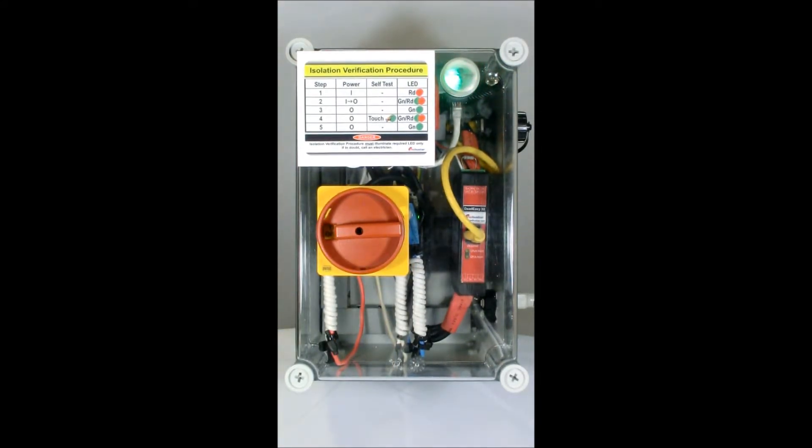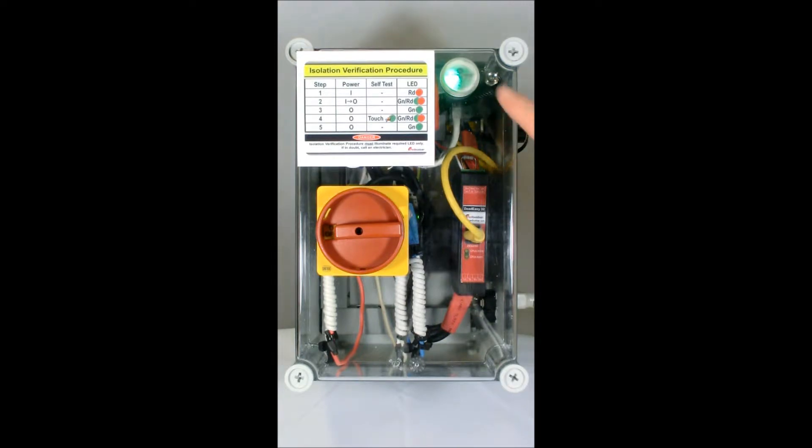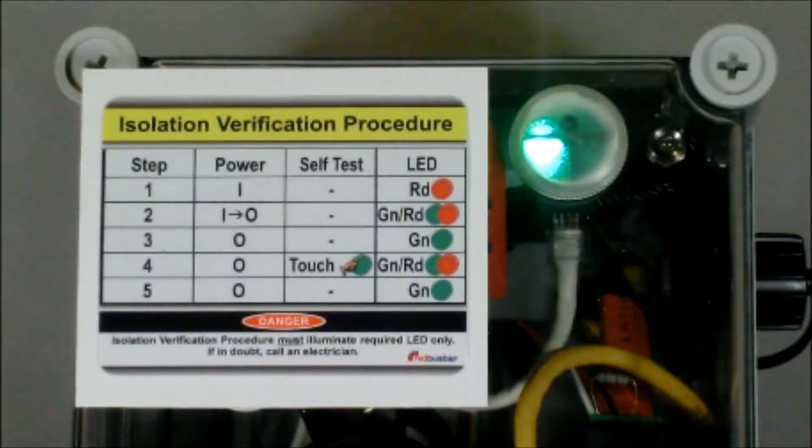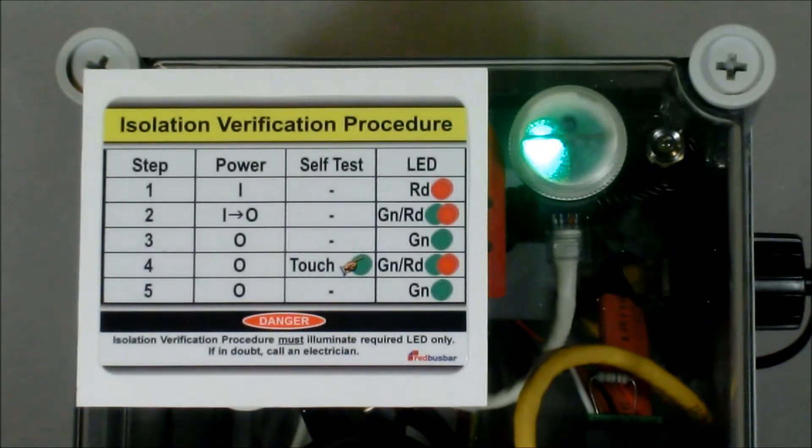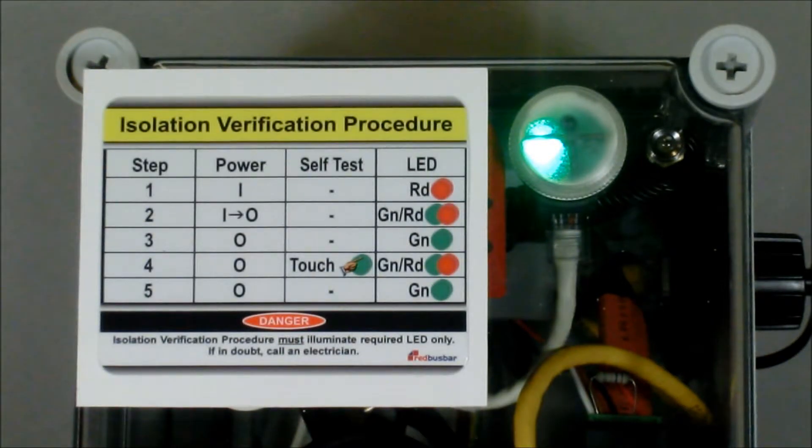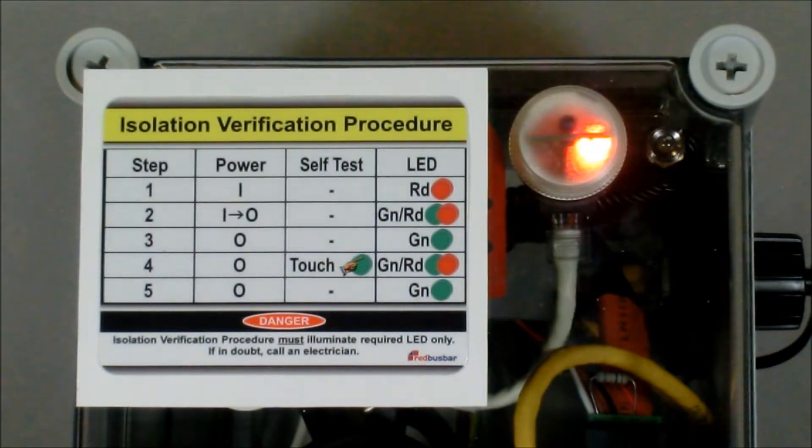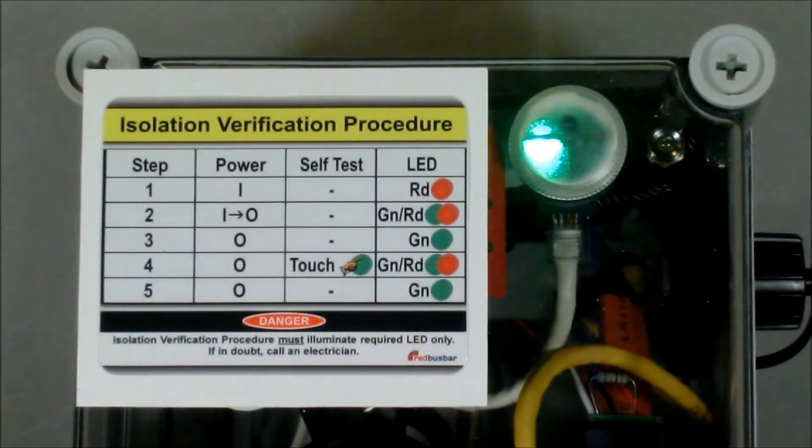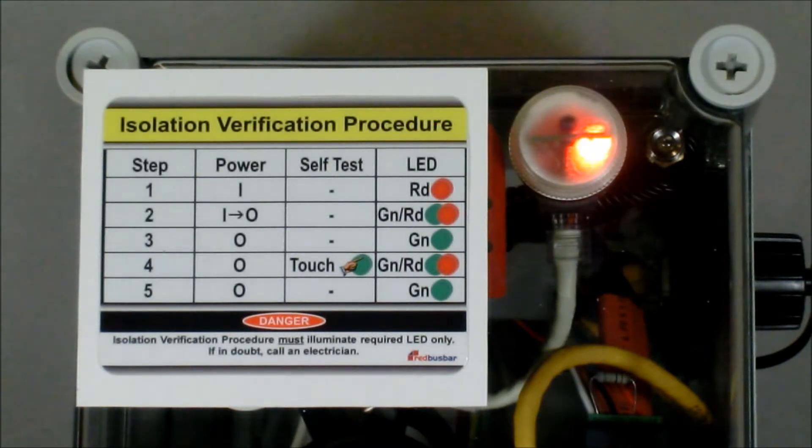This automatic testing is in addition to the manual testing capabilities while the green LED is illuminated. Every proof test performs a sequence of tests. Firstly, the master channel generates a test voltage, which the slave channel expects to detect. Secondly, the master channel removes the test voltage, which the slave channel is expecting to see removed.